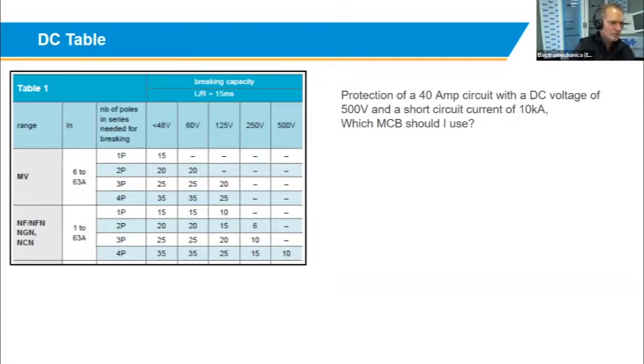Then we do get a lot of questions on DC applications. So the question is, can the Hager miniature circuit breakers be used in DC applications? And the answer is yes. In Annexure 9 in the Electromechanica catalog at the back, there's a DC table at the back that you can use for this application. So a customer wants to protect a 40 amp circuit breaker with a DC voltage of 500 volts and a short circuit current of 10 kA. So which MCB should he then use?